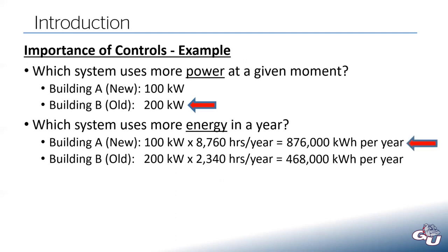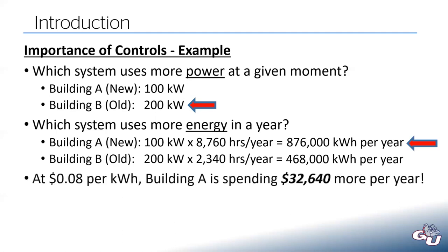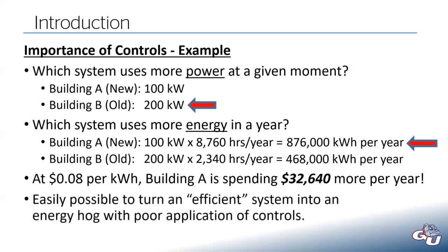So even though that first building, with much more, I'm using air quotes, efficient systems, is being operated in an inefficient way, it is using substantially more energy. And if we were to assume about 8 cents per kilowatt hour, which is about where we're at here in Spokane, building A, that new building, is spending about $32,000 more in energy costs. And so it's very possible to take this very efficient system, at least on paper, hey, everything's brand new, state of the art, but if they operate it in a bad way, using poor application of controls, in this case, not scheduling the equipment properly, well, now this new building is this giant energy hog.